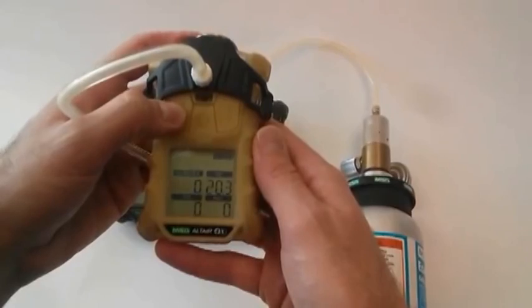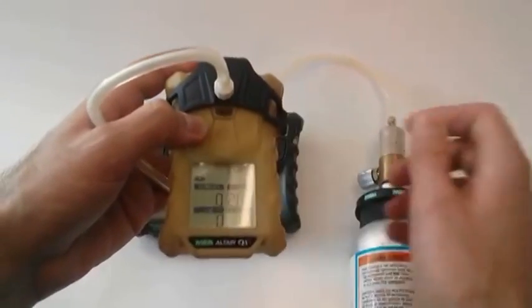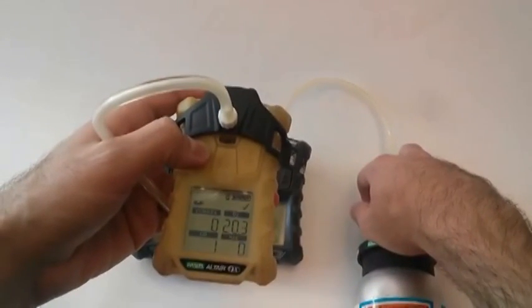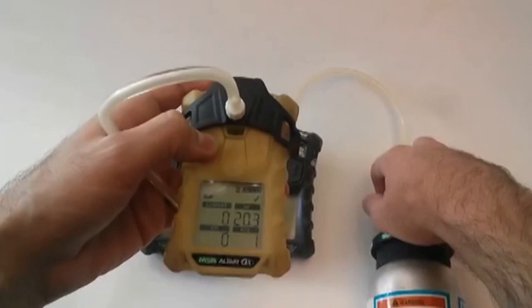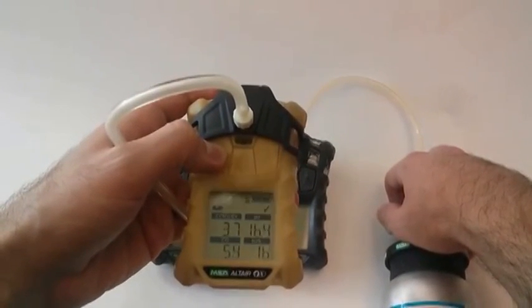And to do your bump test, here we go. You're going to hit the down button. It's going to ask you if you want to do a bump. Hit the power button to acknowledge, and immediately open up that valve to pass over the calibration gas. You see the little icon there telling you to apply gas, and your check mark flashing with the hourglass.